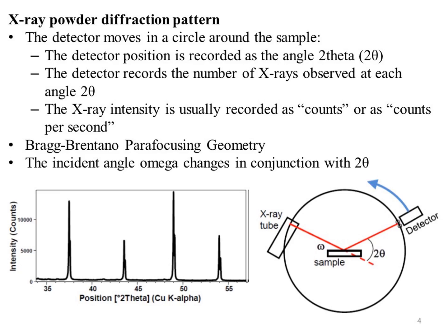This is the geometry of the Bragg-Brentano parafocusing instrument. This is the X-ray tube, here is the sample, and this is the angle omega. Here is the angle 2-theta. The detector moves 2-theta to record the diffracted beams. As a result, we get a diffractogram, which is a plot of the intensity — as counts or counts per second — against 2-theta.